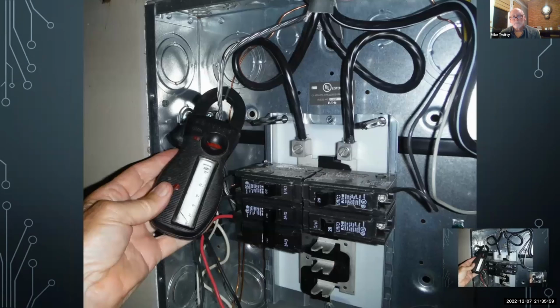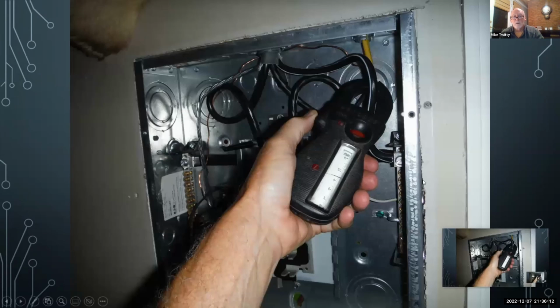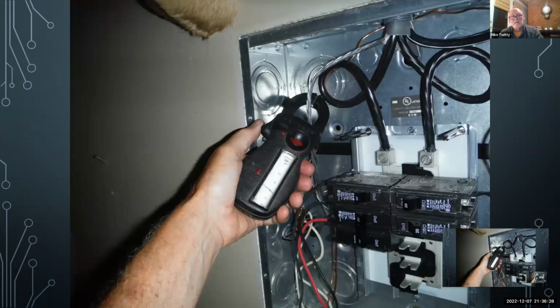Now, still I'm checking the equipment ground, no current on that equipment ground, as it should be. There should be none on there because it's not bonded and they're separated. That's the way it should be. Okay, so now I go in here and I hook it in, I bond it. Same load, read on the service neutral. Now I've dropped to about 10 amps on this service neutral. Well, where'd it go? I still got the same load. There it went. Now it's taking that parallel path back because this sub panel is bonded. That's what happens when they're bonded.